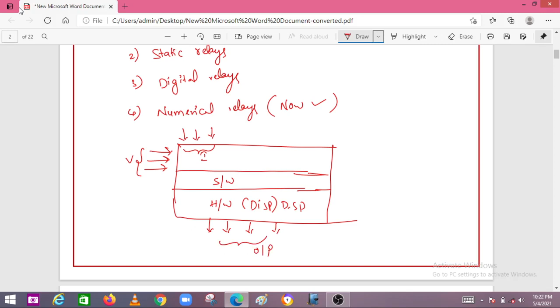So this is a combination of a numerical relay consisting of software and hardware, and in the hardware you will be having some outputs here, and here you will be having some other inputs related to the operation. This kind of relay is used nowadays, called numerical relays, and also it can be called IED, that means intelligent electronic devices. So having certain software related to the relays and hardware components, and a number of inputs, voltage and current, as well as certain other inputs. These are to have certain rated values. For reference purposes, we give rated voltage and rated current, and there will also be outputs. This type of intelligent relay is called a numerical relay or intelligent electronic device. So based on the technology, relays have been classified into 4 types: mechanical relays, static relays, digital relays, and numerical relays.